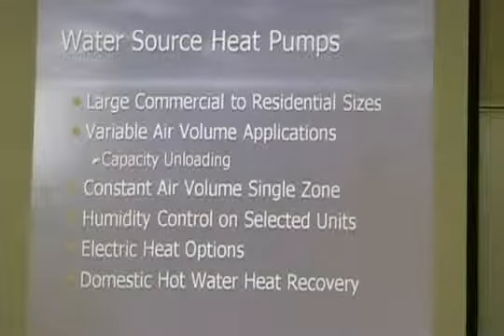You inherently have a little bit of problems with variable volume in DX applications and getting oil return back to the compressors, so you have to be very careful in the minimum airflow that you go down to. You may not be able to turn that unit down to like 50%, but you can still do variable volume applications in the units, say 10 tons and above. They are constant air volume single zone for the most part, meaning that you've got one heat pump per zone.